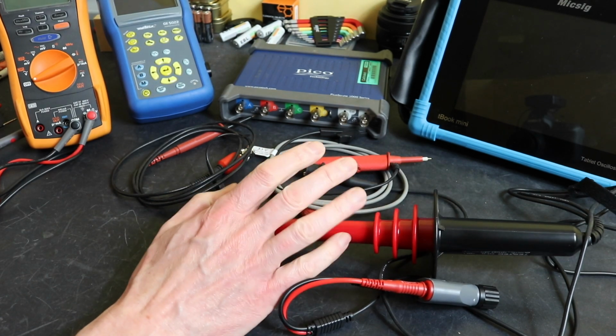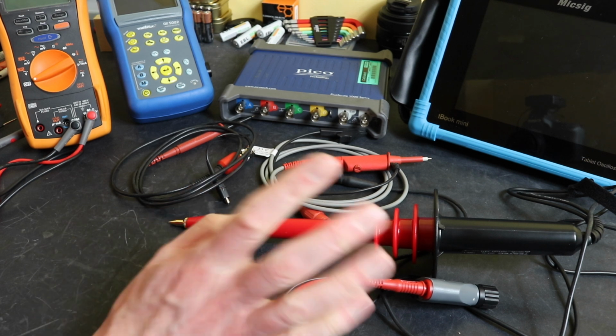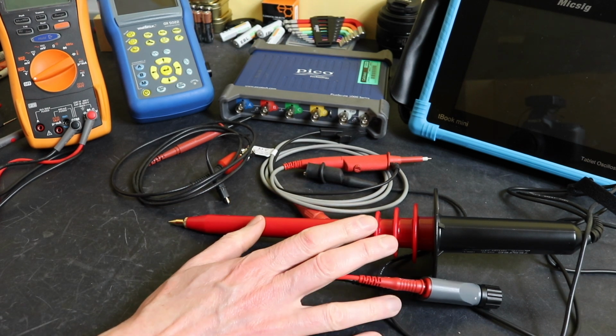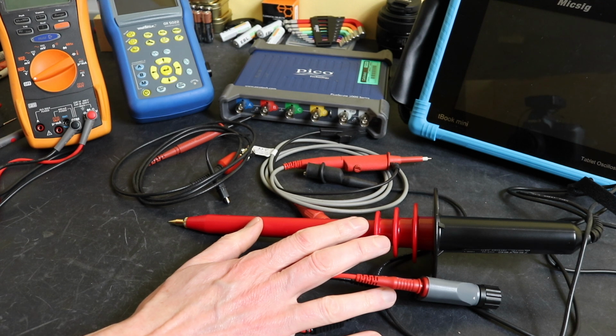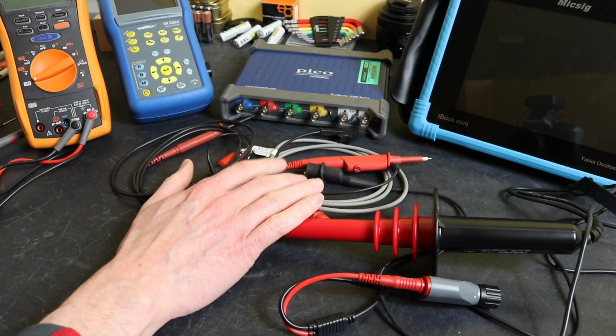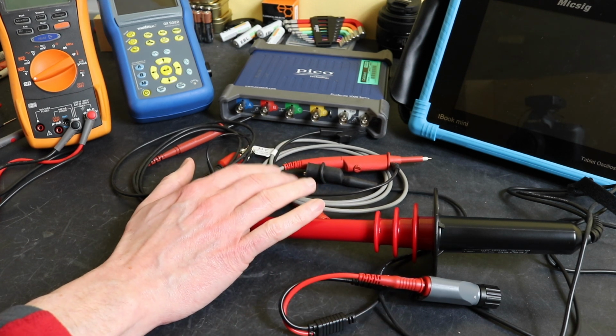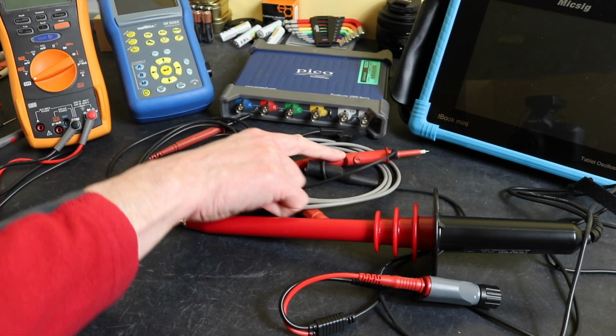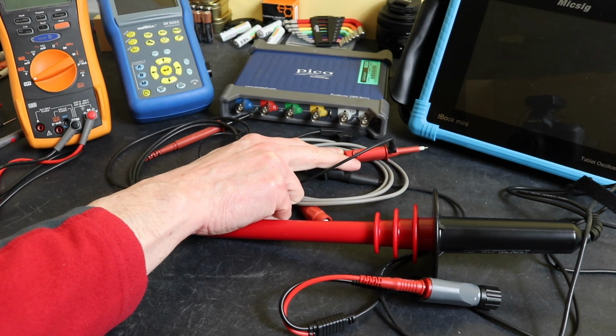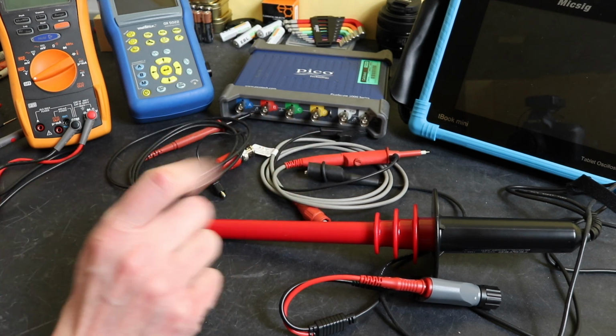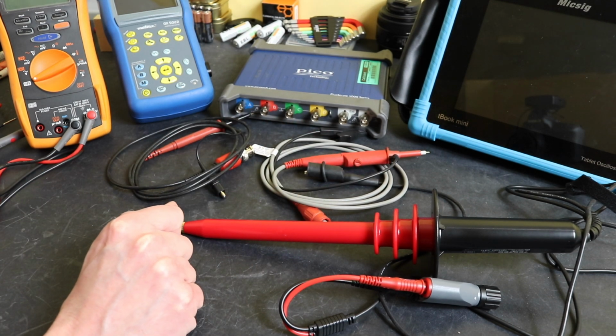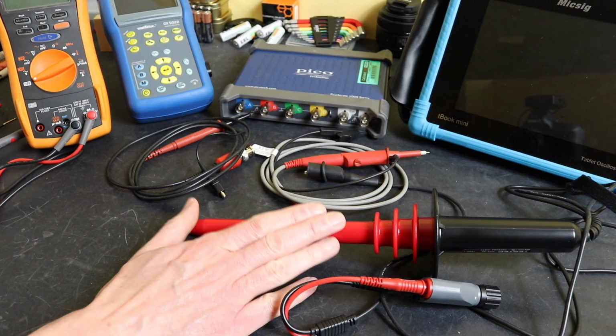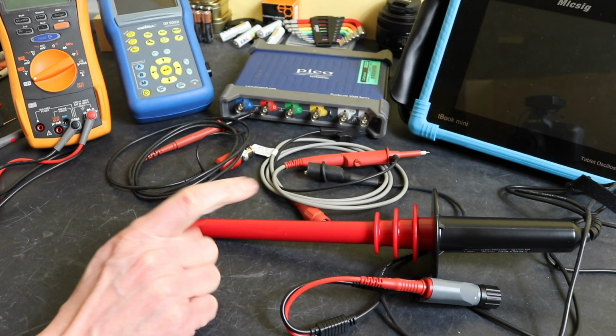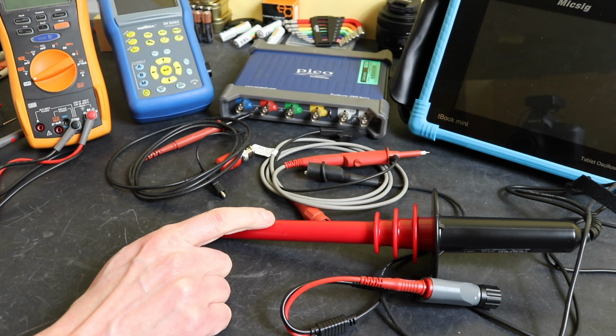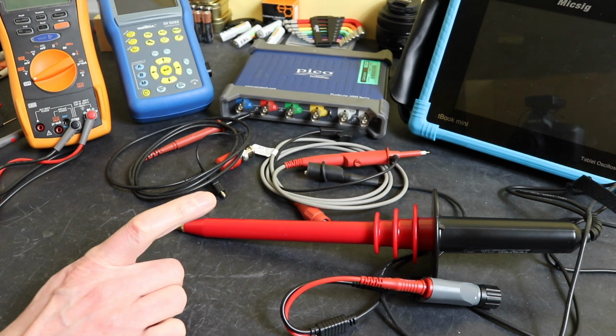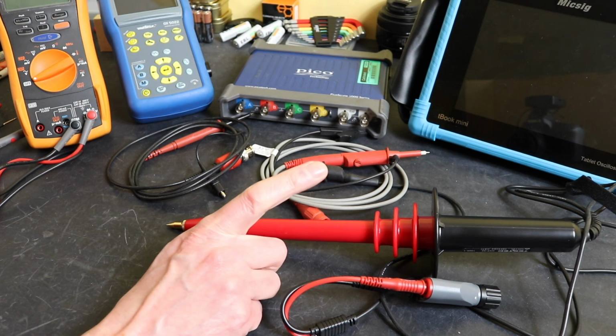There are a few differences though that we can look at with these probes. This is purely a resistive divider. It doesn't have any capacitance built into it whatsoever. Whereas a true oscilloscope probe does have capacitance built into it, and usually an adjustable one. You can see the adjustable compensation there on that probe that allows you to get a true square wave out of the oscilloscope. So this does not have that facility within it. So you could well end up with distortion on your waveform by using this. However, that can be a good thing to note.